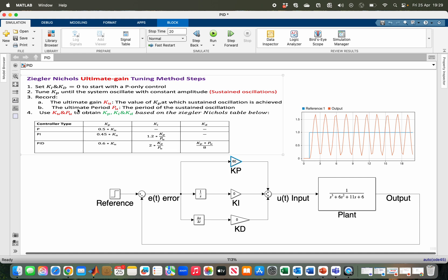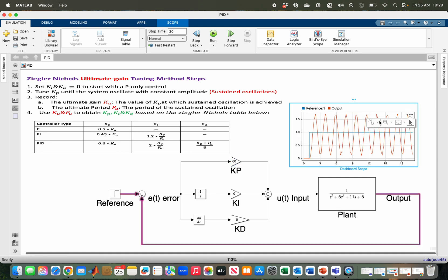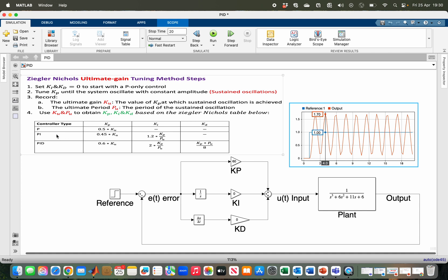The second thing I have to record is the ultimate period Pu, which is the period of the sustained oscillation. I can obtain that by measuring the time it takes to move from first peak to second peak or from second peak to third peak. Let me use my measuring tool using the second and third peak. I have six minus four, which is two seconds, so my ultimate period is two seconds.